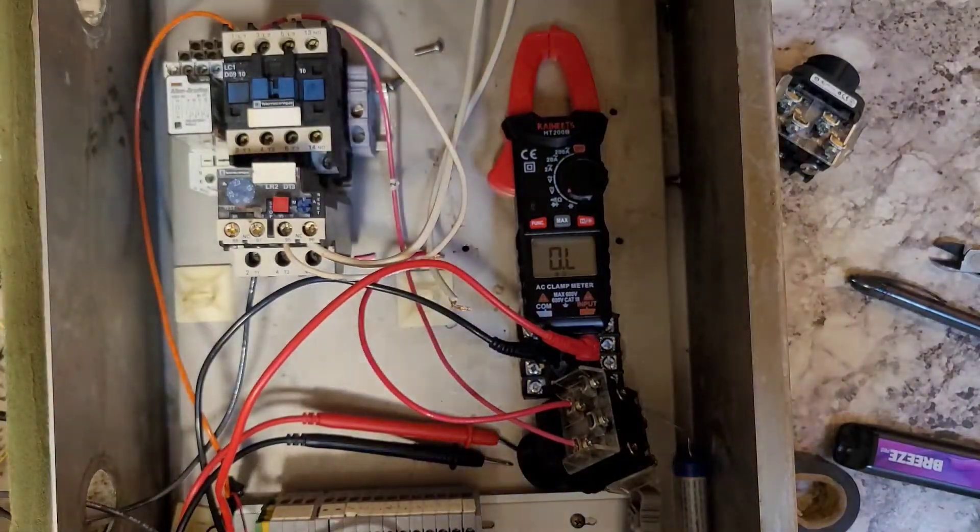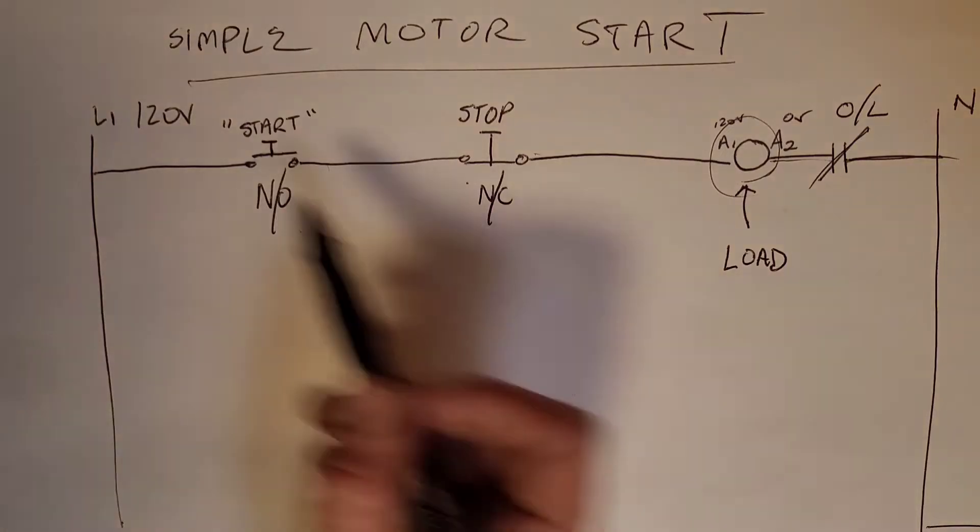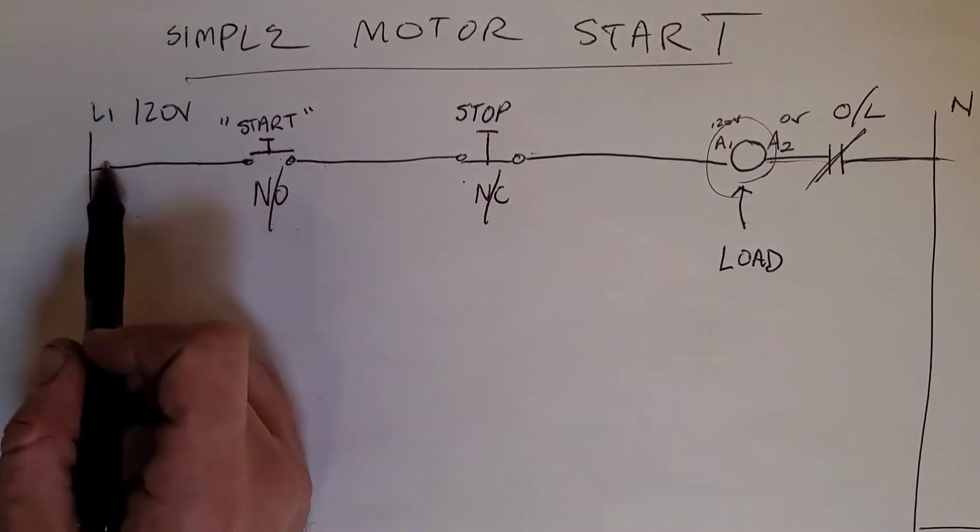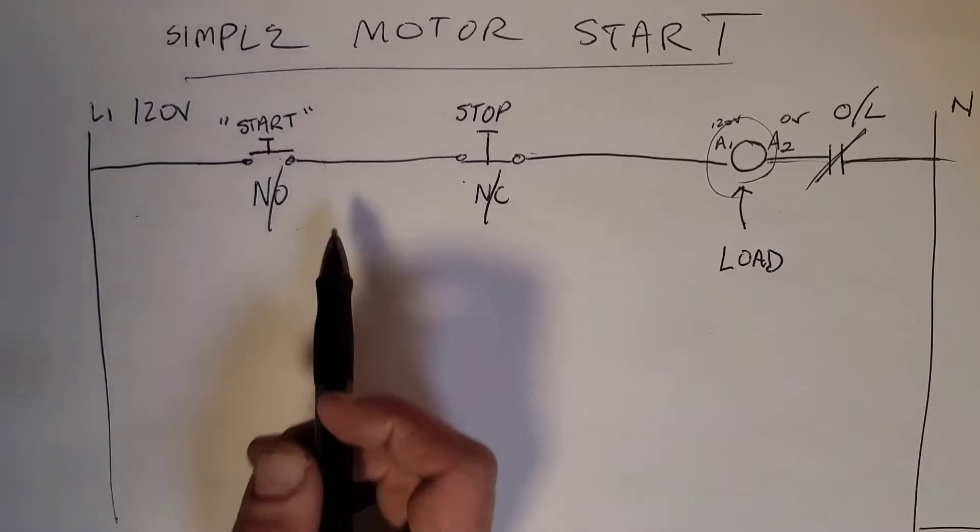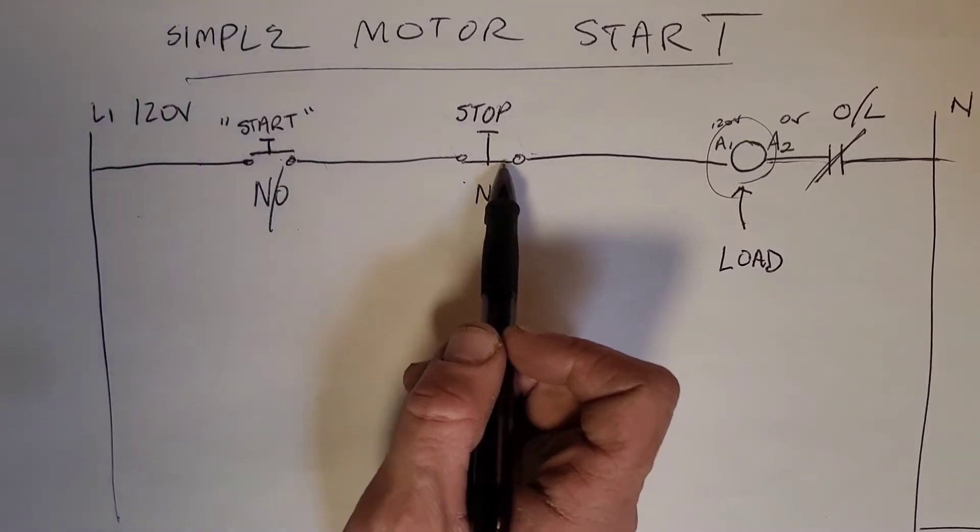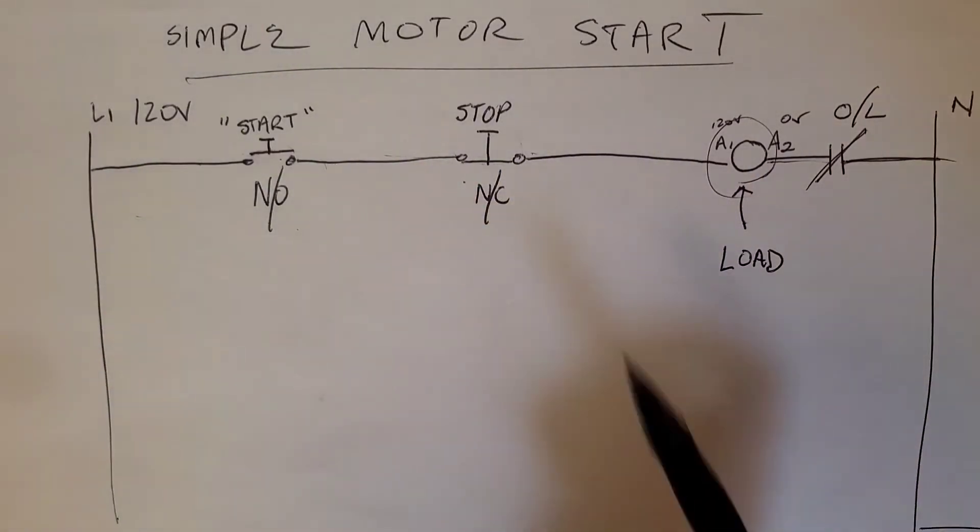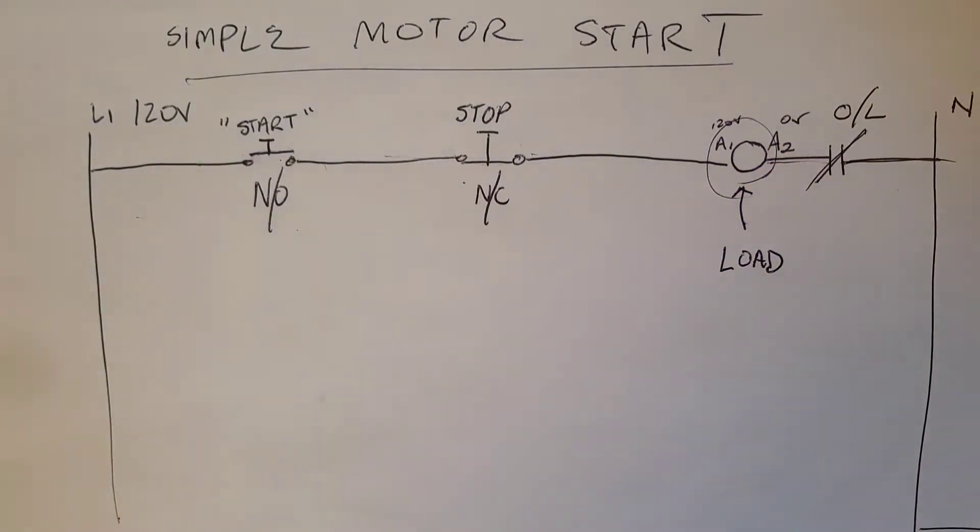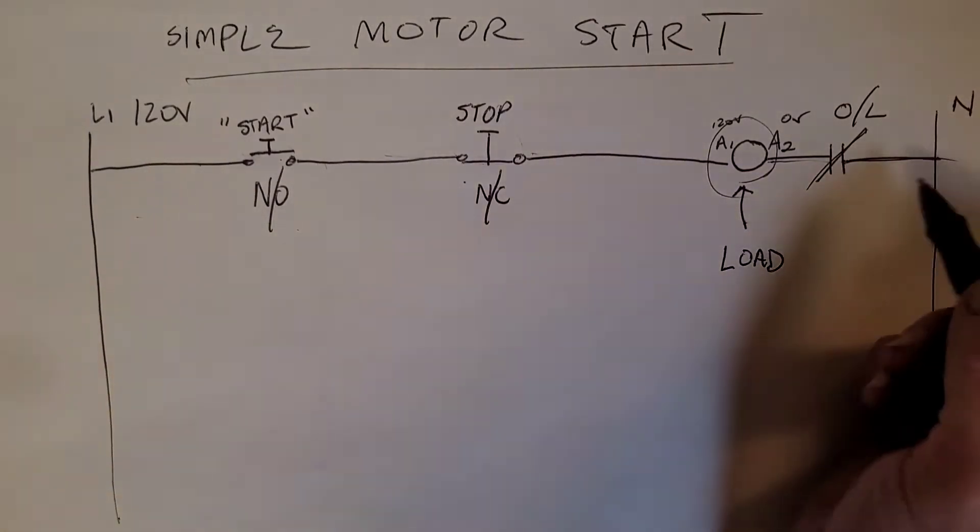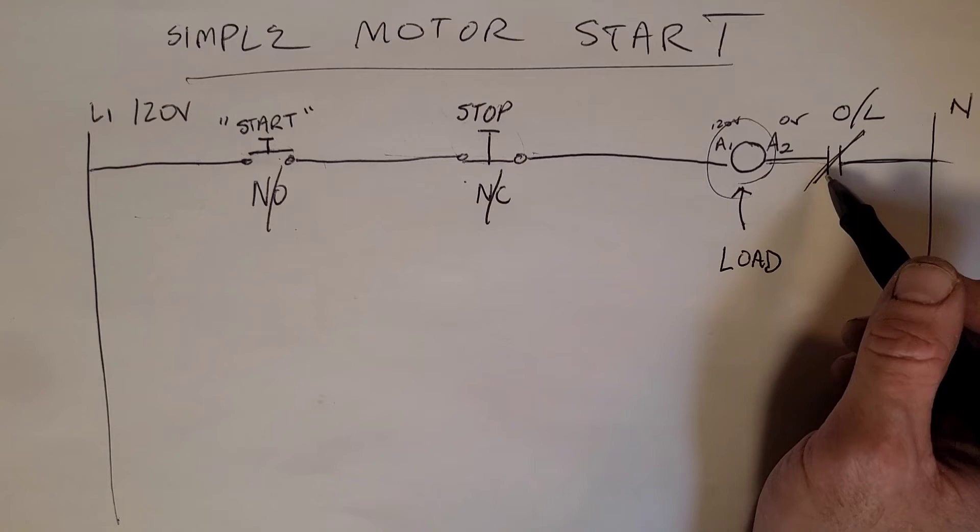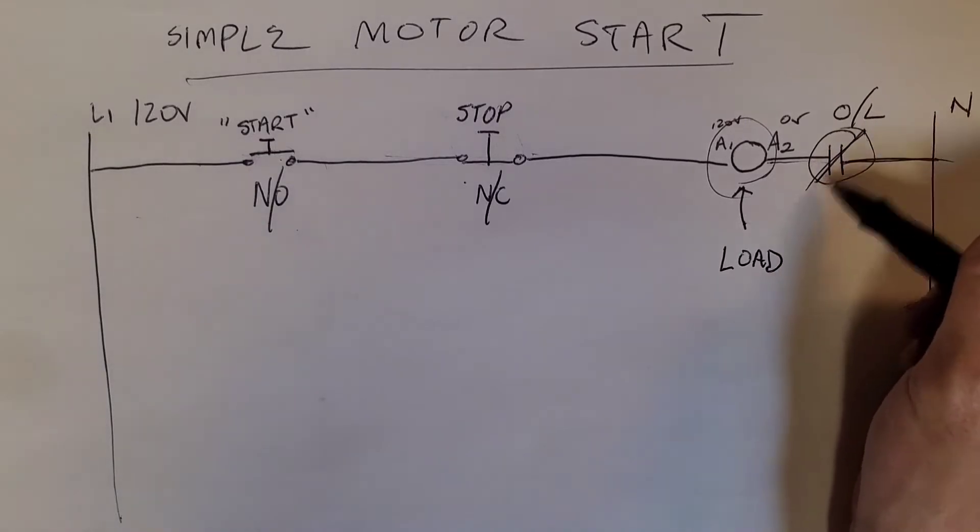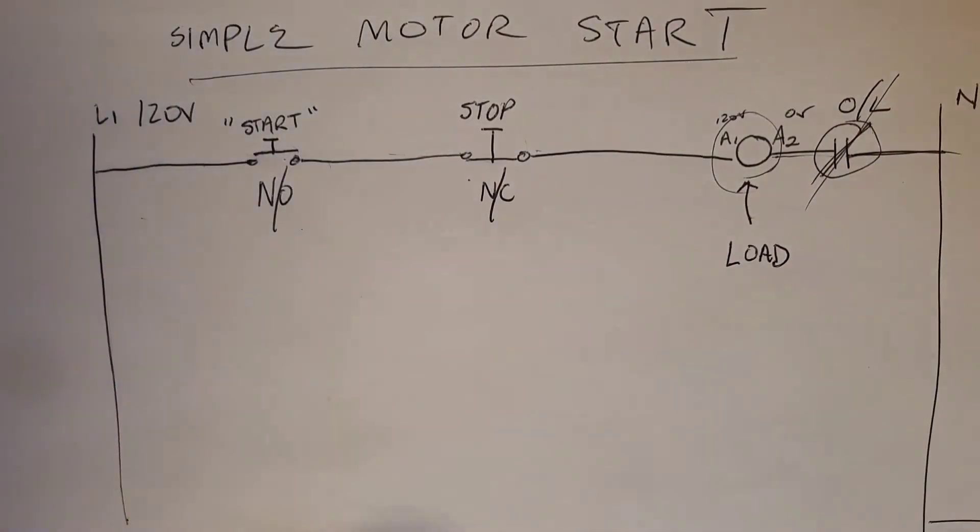To review, we got our motor start circuit right here. Our start button is normally open, so that is going to be dead until we push that in, making it into a closed state, bringing our 120 over here. As long as our stop push button is not pushed, that will continue because it's normally closed, and that will go over A1 and A2, which is our load. Then we're going to go through the thermal overload unit contacts. If there is a high current or over current situation, this set of contacts is going to open up and kill our circuit.